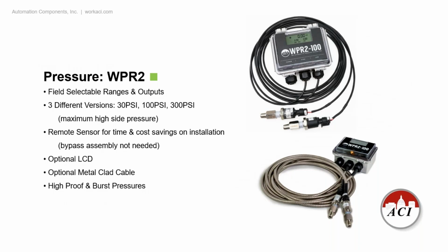Also, a product that we started manufacturing probably about 10 years ago is our WPR2 series. What customers like about this is it has the remote sensors. A lot of our competitors have a sensor that is mounted right on the enclosure itself. So what that means is in the application, you have to run tubing from the pump or whatever you're monitoring, plumbing, tubing, copper line, to each of the sensors, the high and the low. With our unit, you don't have to have plumbing at all.